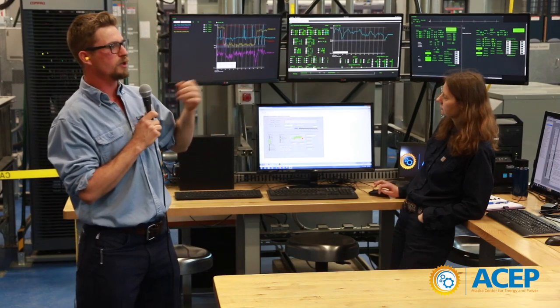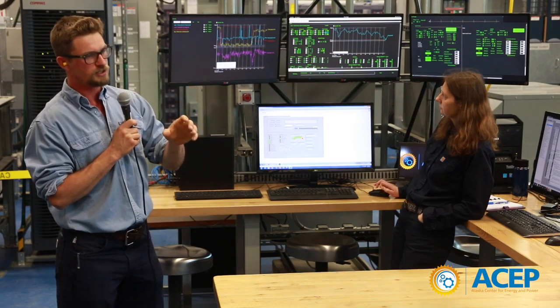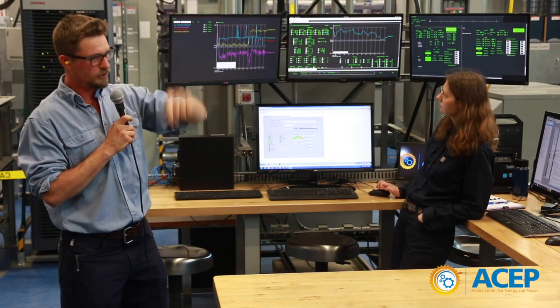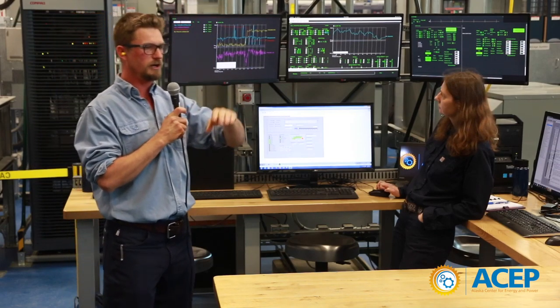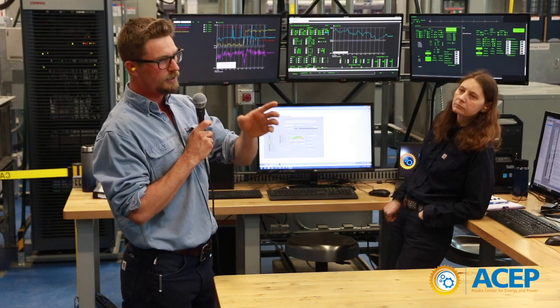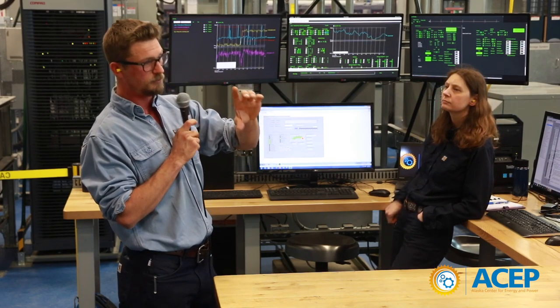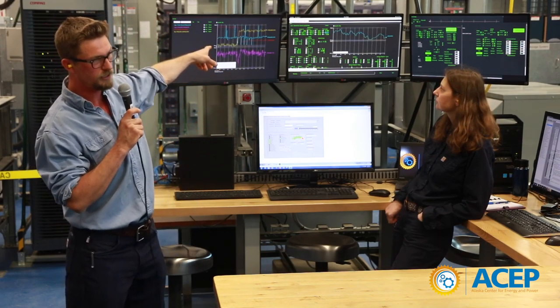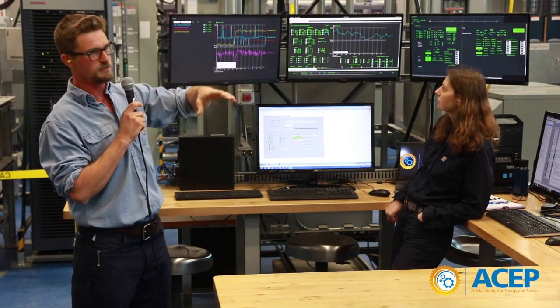The battery is helping improve our power quality. Our power quality wasn't as good because we added all that wind power to the grid — the wind power was ramping the system up and down, and the generator was having a harder time maintaining frequency within acceptable bounds. Now with this inverter and battery on the grid, it can help the generator maintain our system frequency.